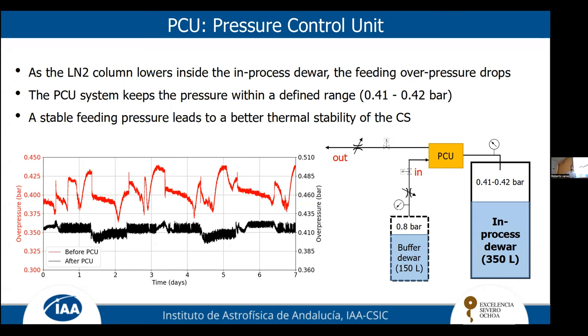It has two working modes. The first one is when the pressure is too high, we basically exhaust the gas to the atmosphere. And when it's too low, we inject gas with this secondary bottle that is called the buffer dewar to the system to keep the pressure in between. We don't do it manually, it's basically automatic.